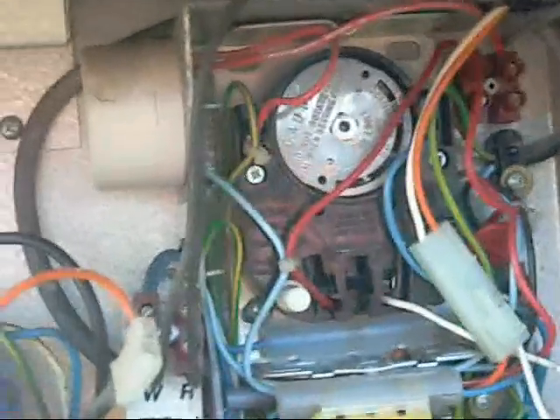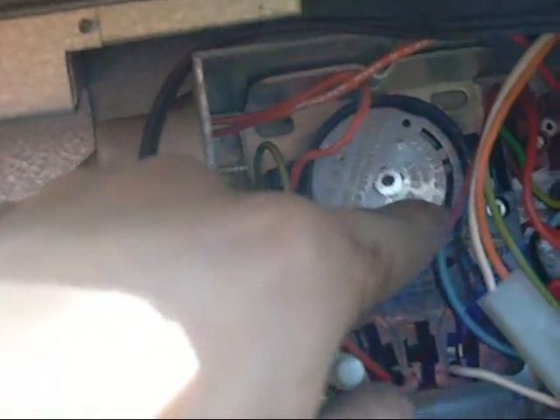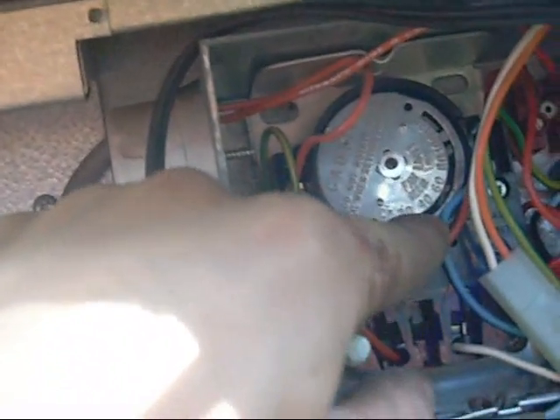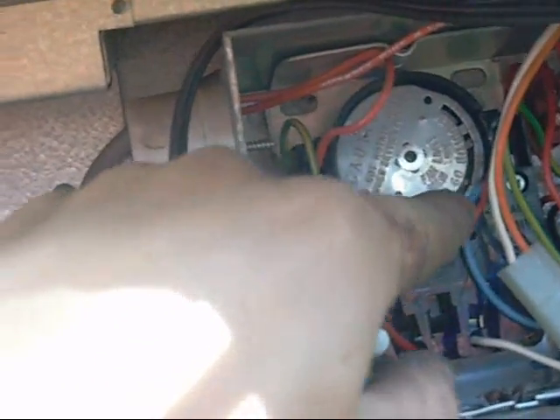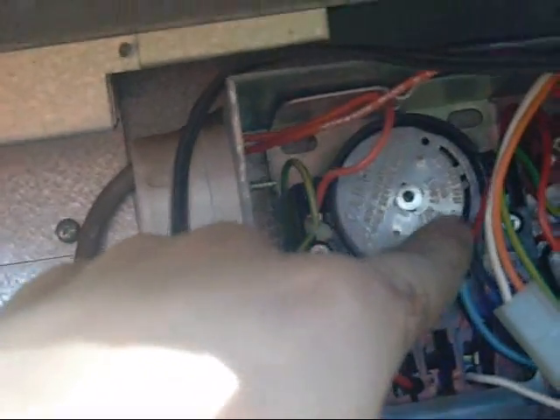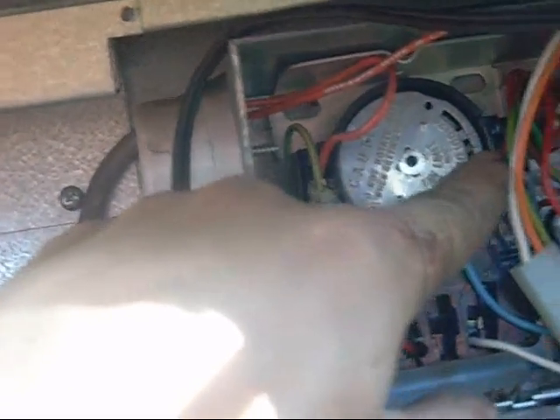And that's the other end of that big probe. That's a temperature limiting system. As the coil of wire inside the end of that probe heats up, this dial rotates, and these little pointers here control limit switches for fan off at, it's about 30 degrees, on 60, about 90, that might be a critical cutout, like shut the whole thing down if it's overheating. Let's say that's what it would be, it's a safety cutout.